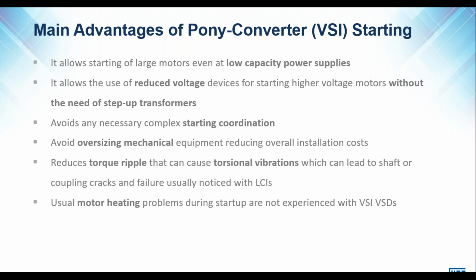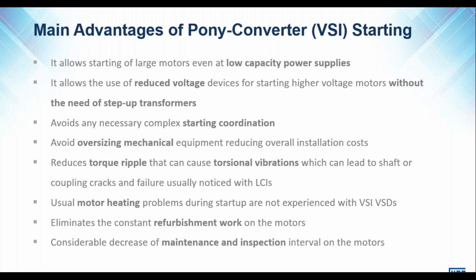The usual motor heating problems during startup are not experienced with VSDs, again, because we can control both the starting torque and acceleration time. It eliminates the constant refurbishment work on the motors and considerably decreases maintenance and inspection intervals.